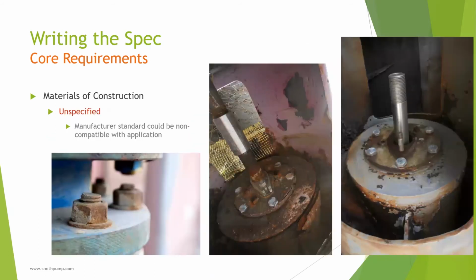Forgetting to list the material requirements is like playing the lotto. If materials are unspecified, you'll get the manufacturer's standard material, which could work for the application or it might not. 2 very common upgrades we normally recommend are hardware and shafting to stainless steel. These items are typically standard in carbon steel for most manufacturers. Sometimes carbon steel shafts corrode enough in service that they must be torched off during disassembly. So at that point, we just replace them with stainless so it doesn't happen again.